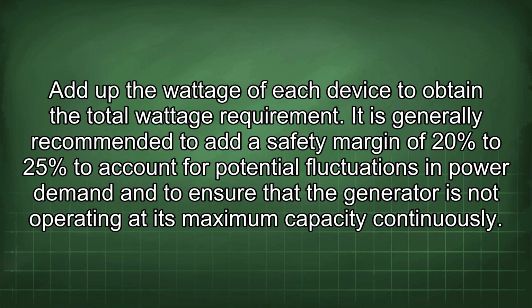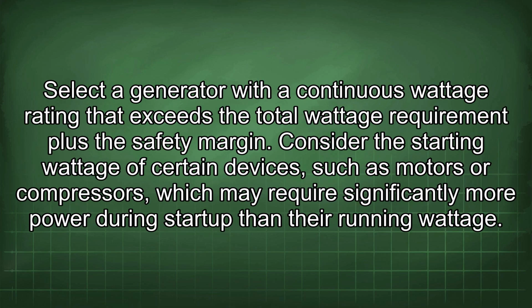It is generally recommended to add a safety margin of 20% to 25% to account for potential fluctuations in power demand and to ensure that the generator is not operating at its maximum capacity continuously. Select a generator with a continuous wattage rating that exceeds the total wattage requirement plus the safety margin. Consider the starting wattage of certain devices, such as motors or compressors, which may require significantly more power during startup than their running wattage.